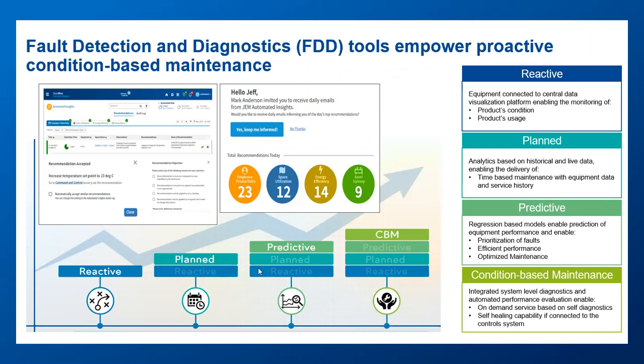Some FDD solutions stop after detecting the fault but are weak when it comes to automatically diagnosing the real root cause versus just listing 6 or 10 potential causes. That's something you want to focus on in your strategy or requirements for an FDD solution. It's also important that FDD solutions automatically help prioritize faults based on cost impact, potential impact to critical patient care, duration the fault's been active, etc. Without that automated prioritization, the list becomes too overwhelming and doesn't really help the facility operator become more proactive, which was the original goal.